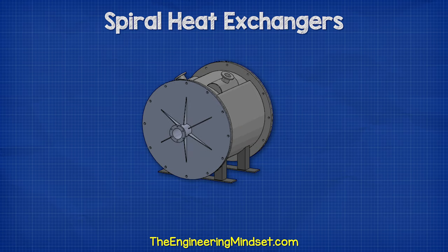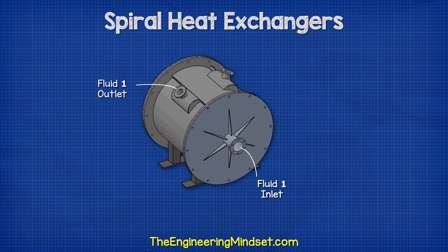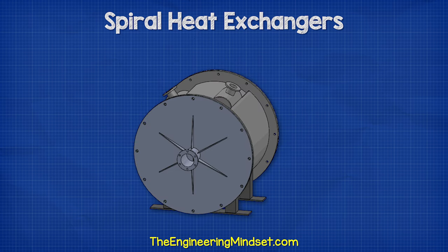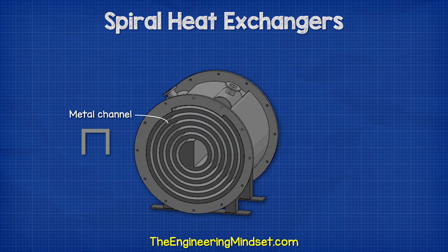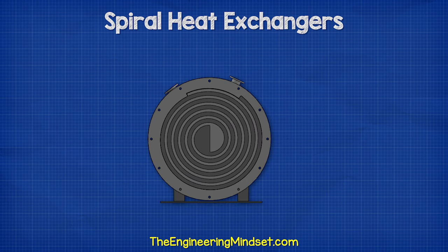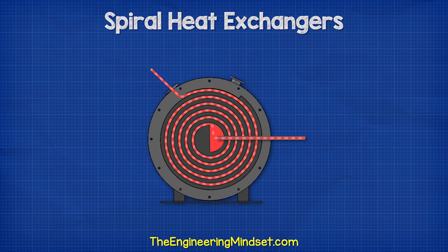Spiral heat exchangers look something like this. We have a flanged inlet on the front face with the outlet located on the top. Then we have an inlet from another fluid also on the top with the outlet located on the rear face. Behind the end plates, we find two sheets of metal inside which spiral together around the interior to form a channel which the fluids will flow through. The channel completely separates the two fluids. We see the first fluid enters the heat exchanger and fills the chamber, then flows around the channel and to the outlet.